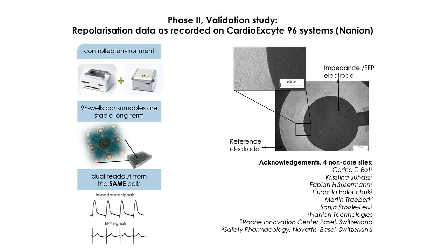This is what the CardioExcyte system looks like. It's sitting outside of the incubator. It has this incubation lid here on top, so it's a controlled environment. We have 96 well plates, and basically the electrode design here allows combined recordings of both impedance and EFP.